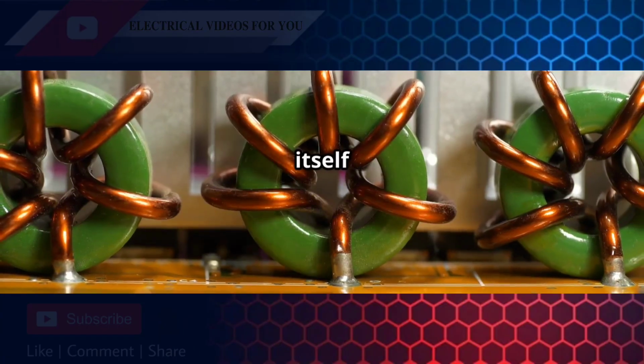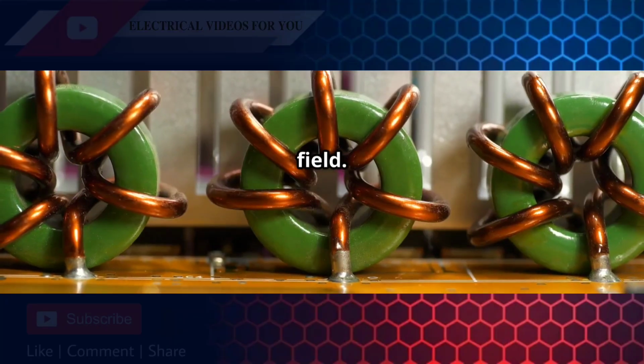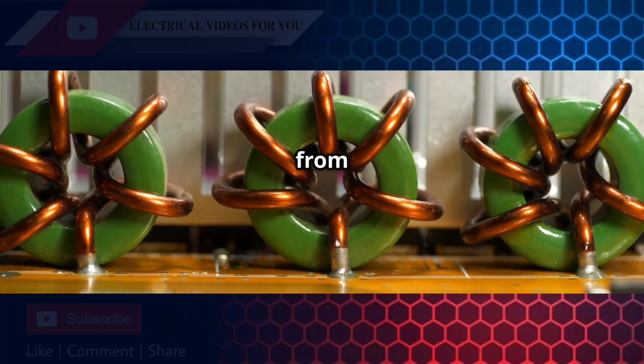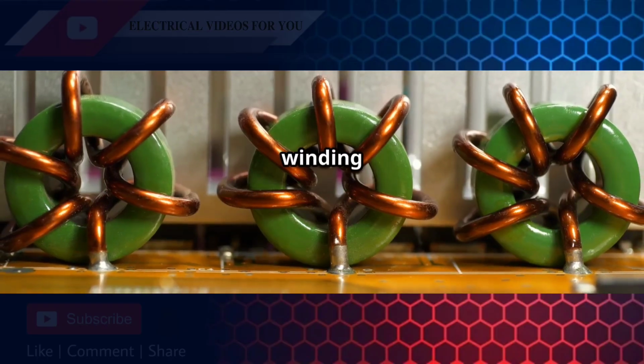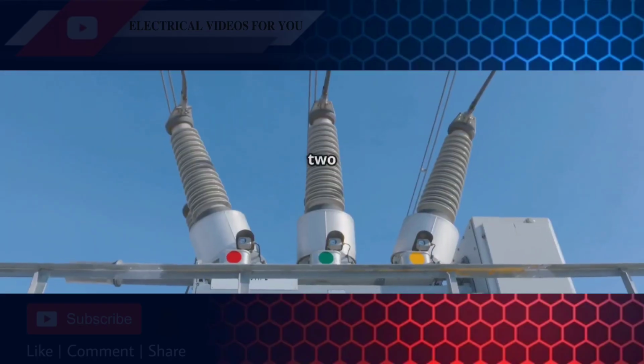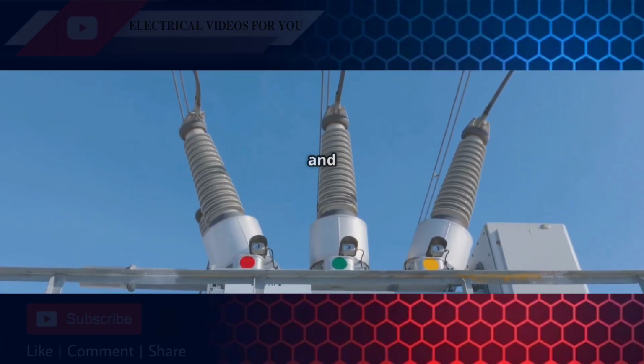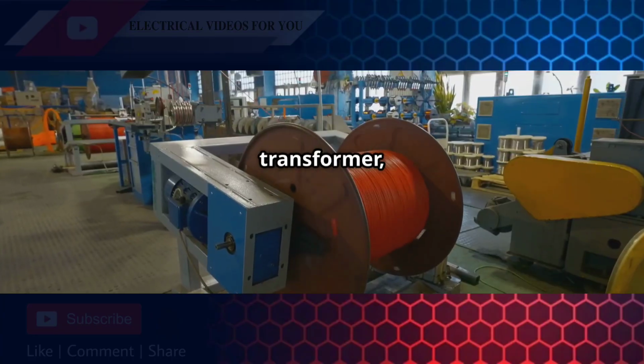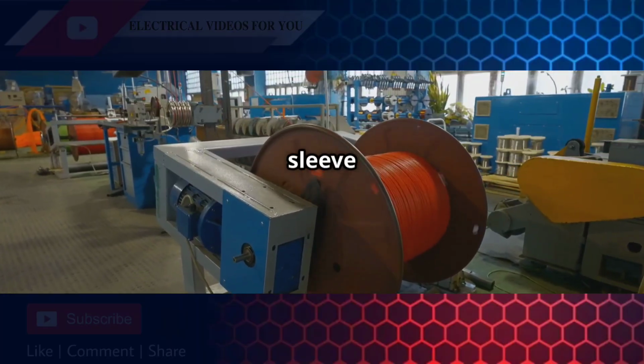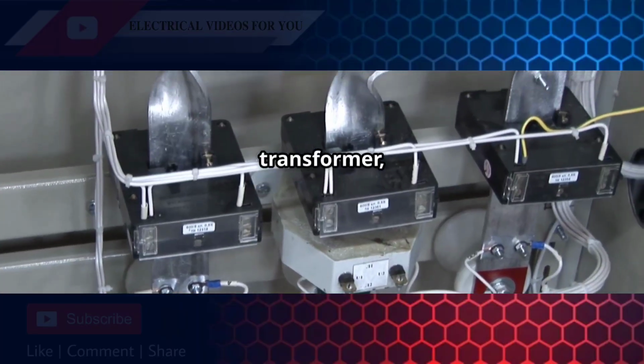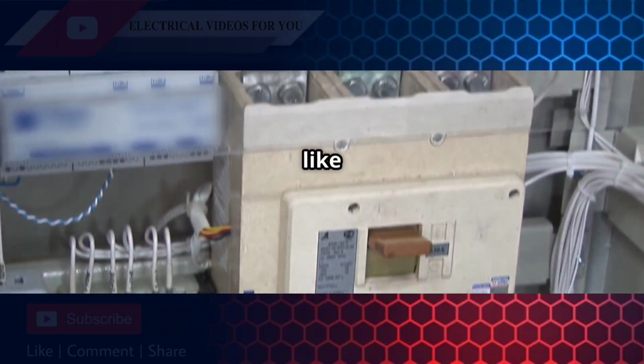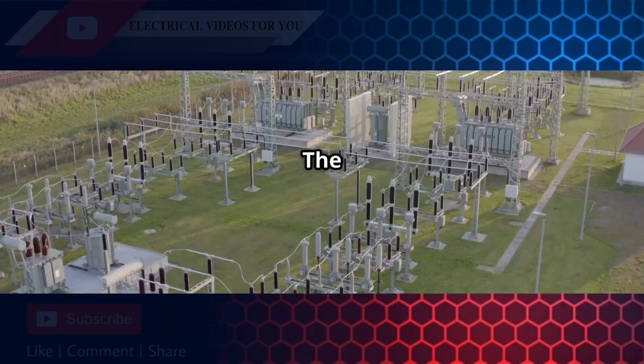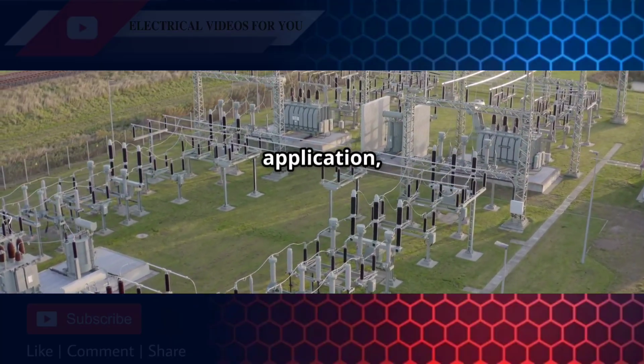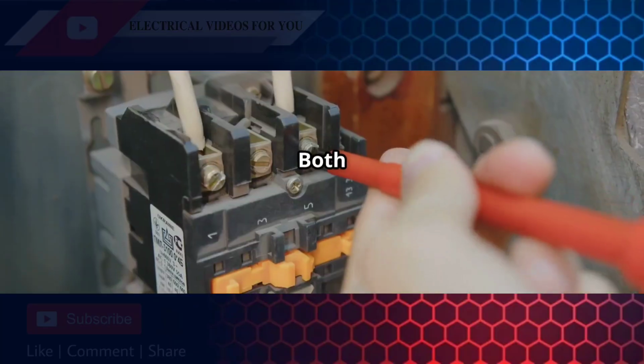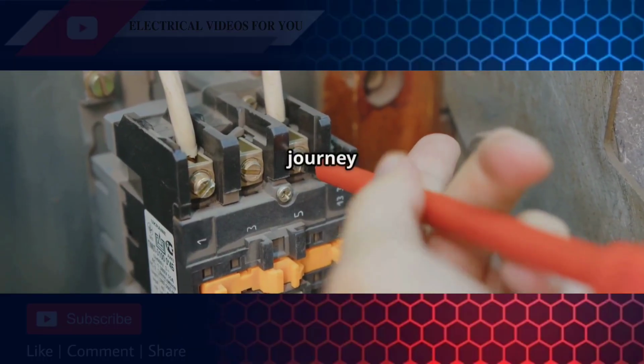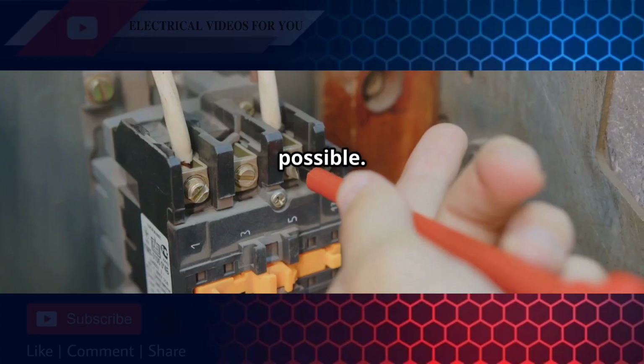The transformer core itself is the pathway for the magnetic field. Its job is to guide the magnetic flux from the primary winding to the secondary winding with as little loss as possible. There are two main types of cores, the core type and the shell type. In a core-type transformer, the windings surround the core like a sleeve on an arm. In a shell-type transformer, the core surrounds the windings, like a shell protecting its contents. The choice between them depends on the application, voltage, and power rating. Both designs are engineered to make the magnetic journey as easy and efficient as possible.